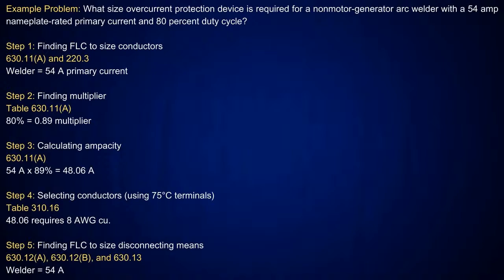All right. Now, when you go over and look at 630.11a, it's going to tie you in with table 630.11a, and that's where you're going to get your duty cycle multiplication factors for the arc welder. So this, once again, and think about what I'm saying here, it's just like the AC unit. That is what? An assembly. It comes as one unit. So you're going to use the nameplate value here. Okay. So in this case, I've got a non-motor generator arc welder.